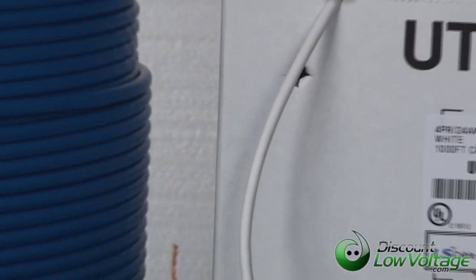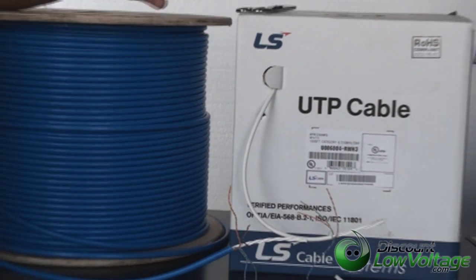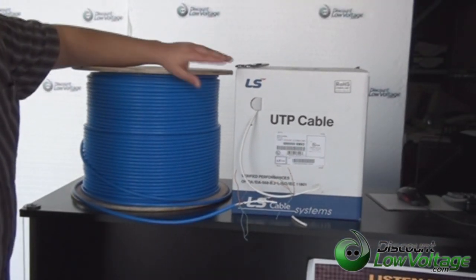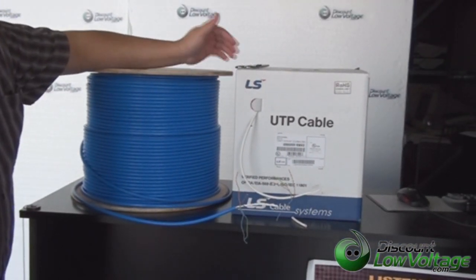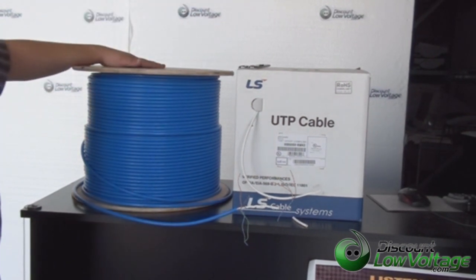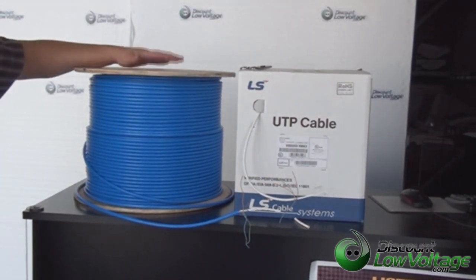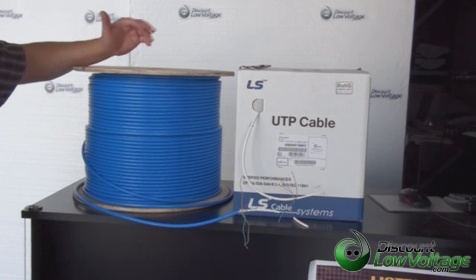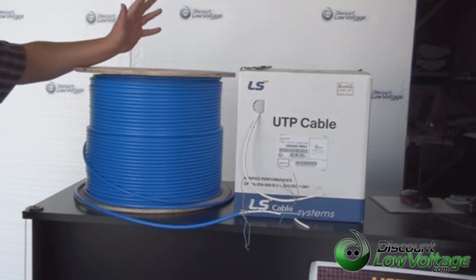Now another issue with this cable is the weight from one to the other. The Category 6 cable typically about 33 pounds a thousand. Category 6A, this spool right here, is 53 pounds a thousand.